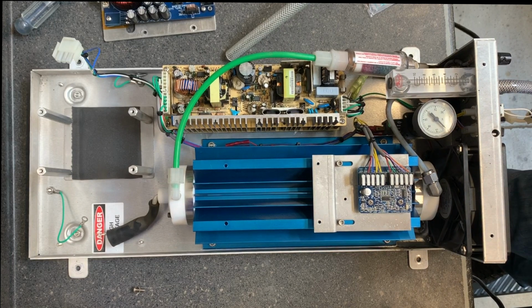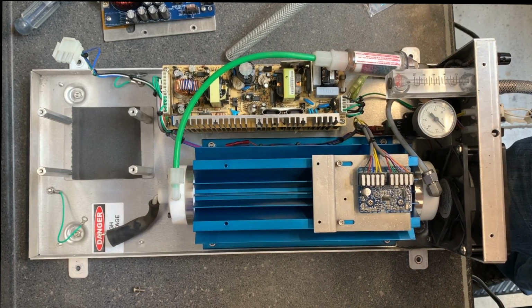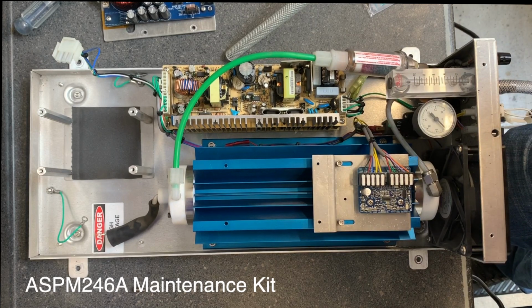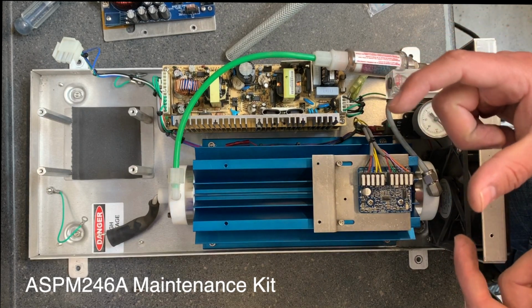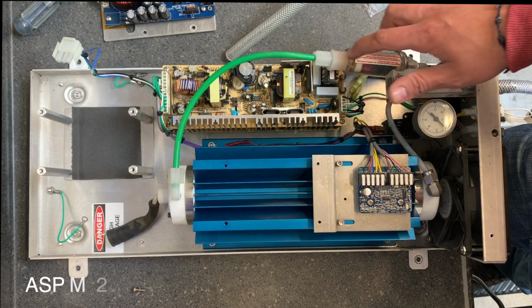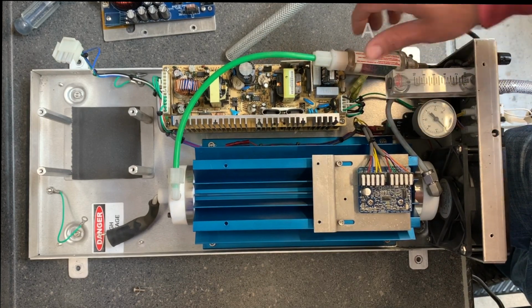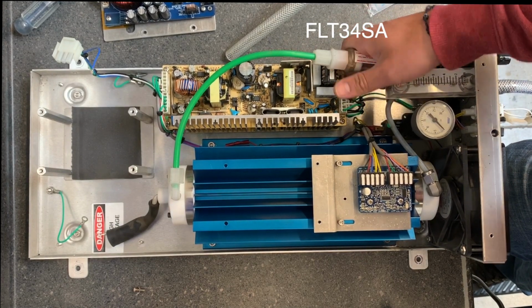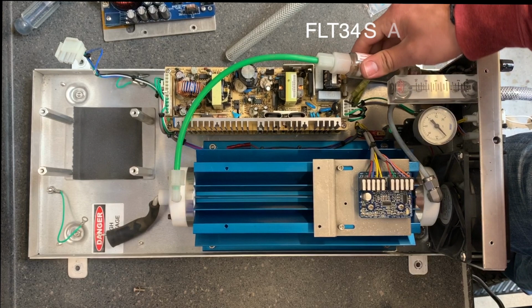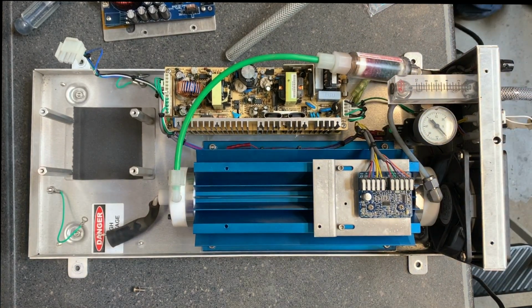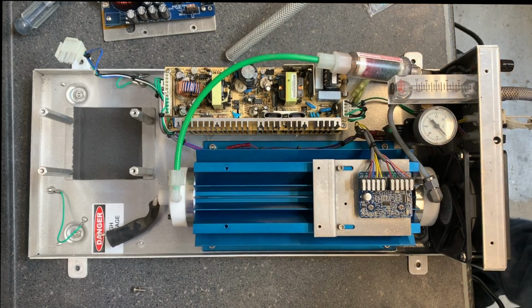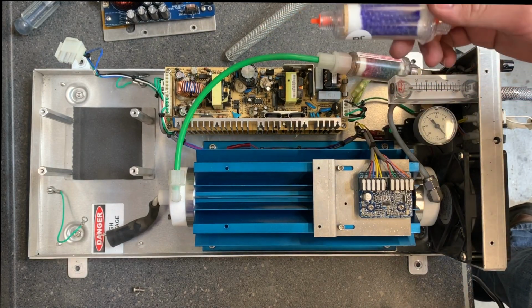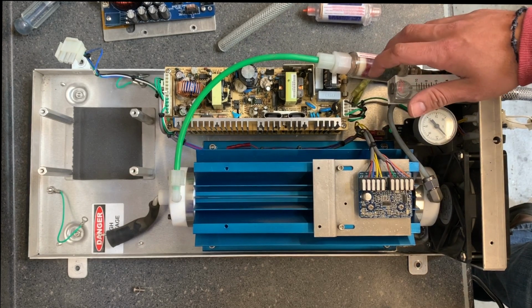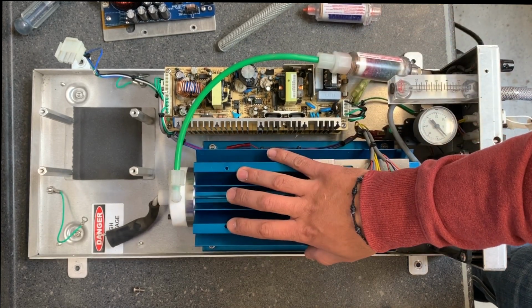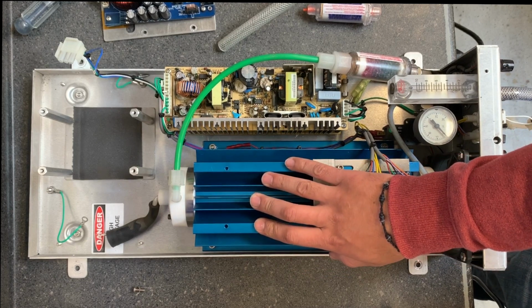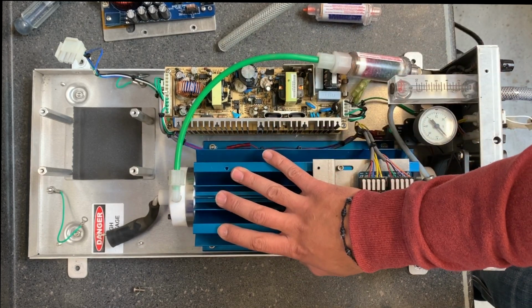So next I'm going to show you how to inspect your chamber and rebuild it with your maintenance kit. You'll receive O-rings, a little silicone tube, a fan filter, and an inline filter, which is FLT34. If you go up to your unit and you see this filter turning pink and it's no longer blue, it's a clear sign that a lot of moisture has been going into your unit. This is how it should look when it's brand new or when it's still in good shape. So if you have this color on your filter, most likely your unit needs the maintenance as well. So don't just swap out the filter and not do the maintenance on the unit.